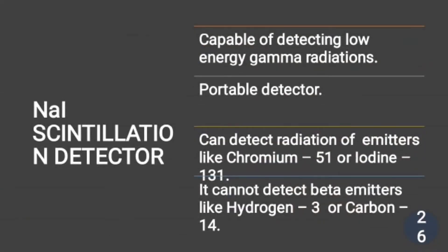Next is the sodium iodide scintillation detector. As the name suggests, the main compound used is a sodium iodide crystal. This instrument is capable of detecting low-energy gamma radiations. Like the Geiger Muller counter, it is also a portable device. It can detect radiations from emitters like chromium-51 or iodine-131. The main drawback is that it is inefficient at detecting beta emitters like hydrogen-3 or carbon-14.